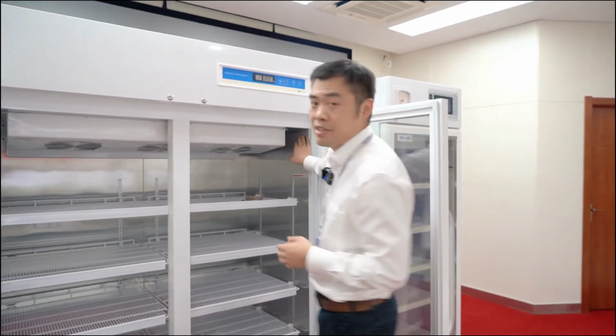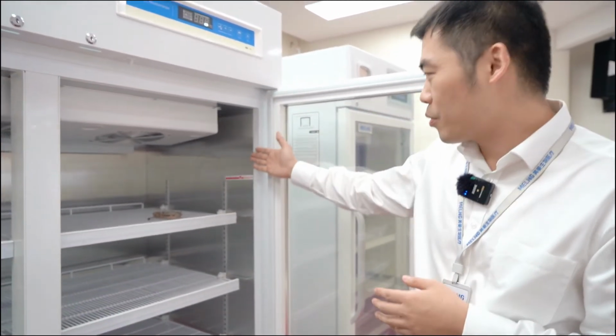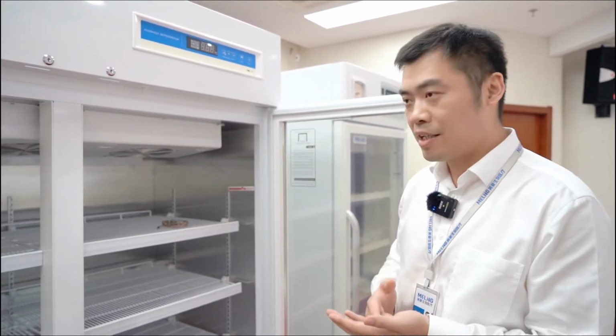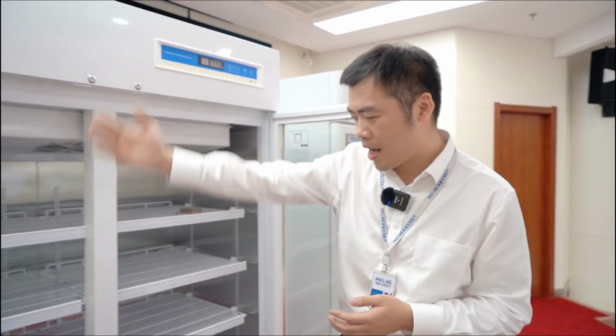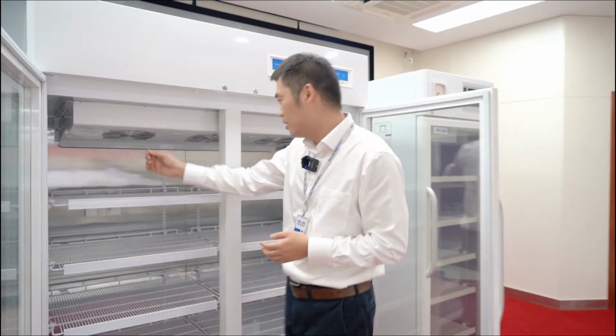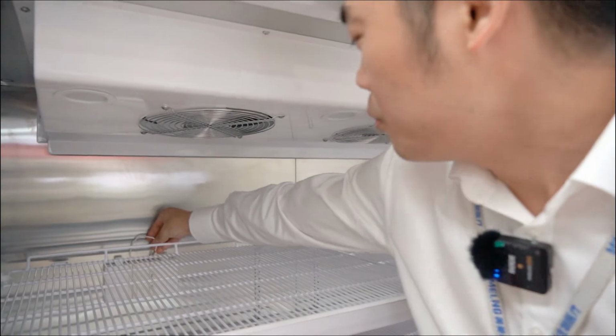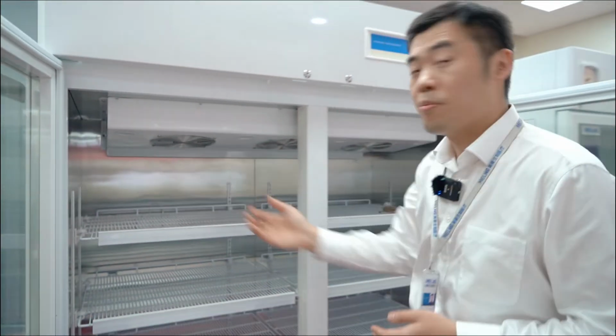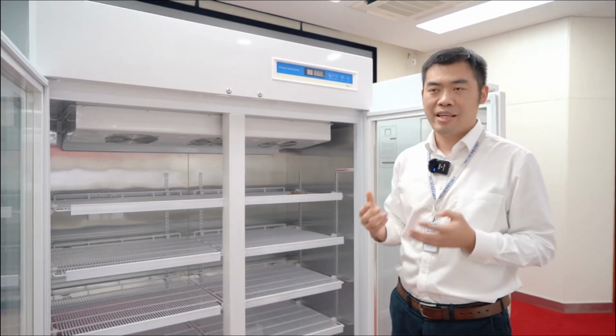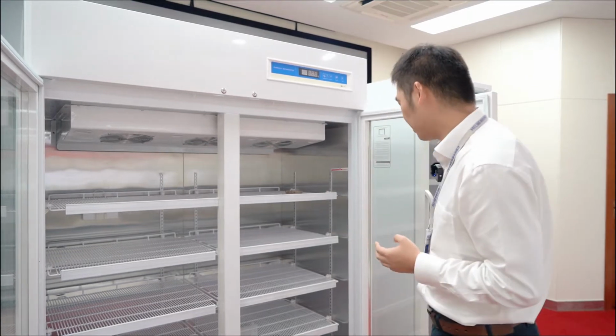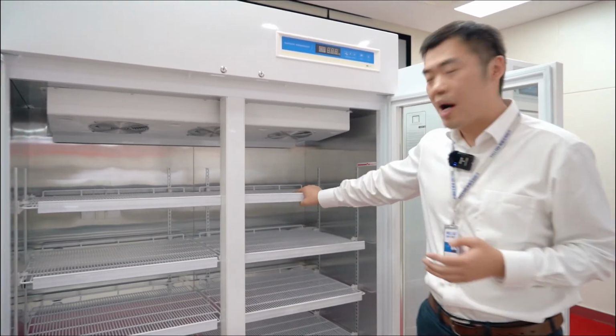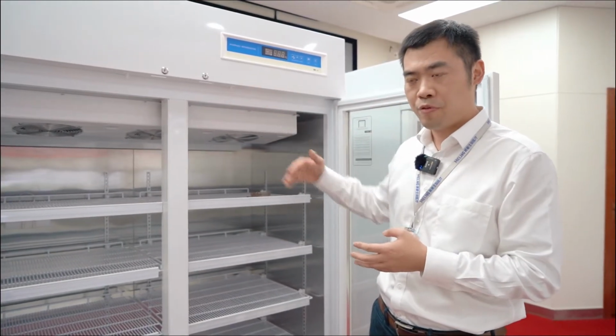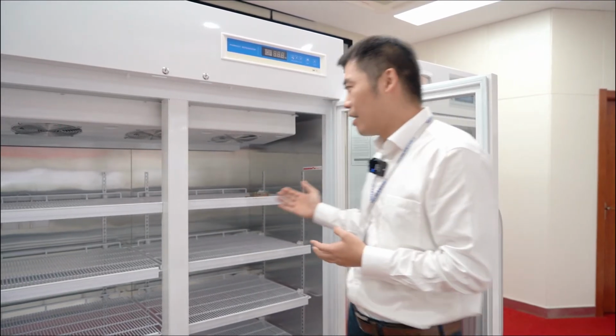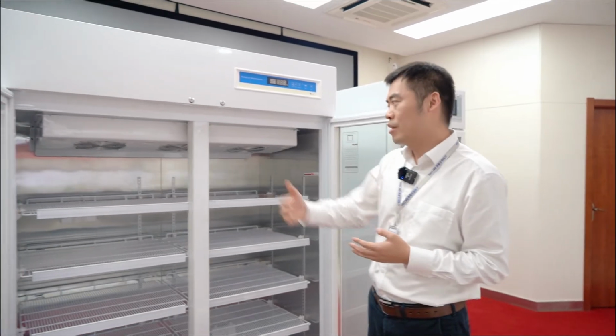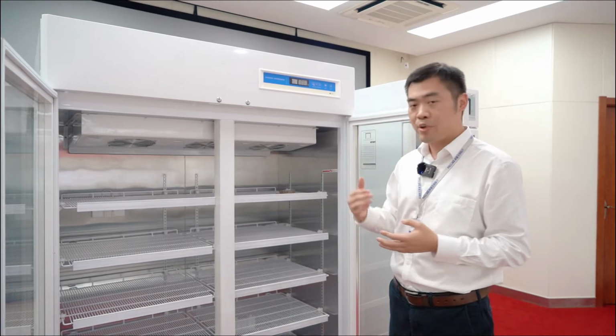Depending on different customer requirements, the cabinet interior could be galvanized sheets or stainless steel. There are a total of 5 probes inside the chamber, and you can see the 2 display probes that we have put into the simulation bottle to make sure the temperature detected is exactly the sample's temperature. The coated wire shelves are adjustable to fit customer modification. And there is no heating defrost system, to maintain very good temperature uniformity.